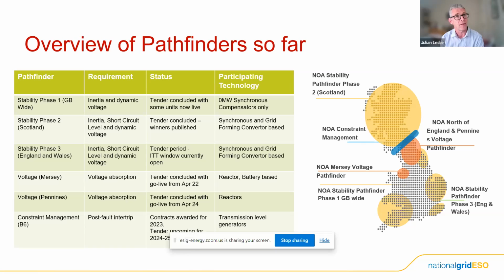But that did mean that in phase two, when we went to the market, we procured 10 devices, 5 of which are traditional synchronous condensers, flywheels, etc., but 5 are batteries with grid forming inverters. So again, really using that new technology to think differently about how we operate the system, providing that short circuit infeed through grid forming. And then phase three, where we're just in the tender process now, looking across GB, again focusing on short circuit infeed and voltage control, but we expect contract award to be later in the autumn or in the fall, just after summer.